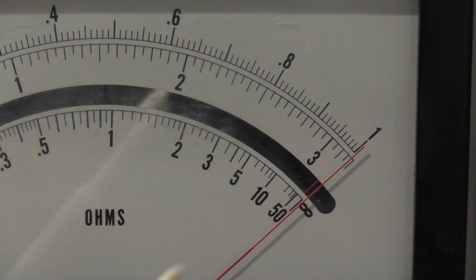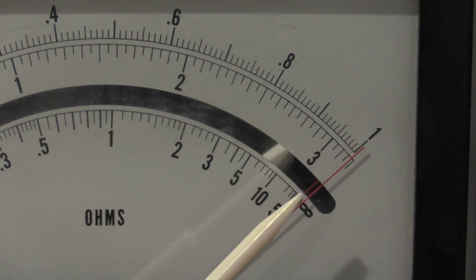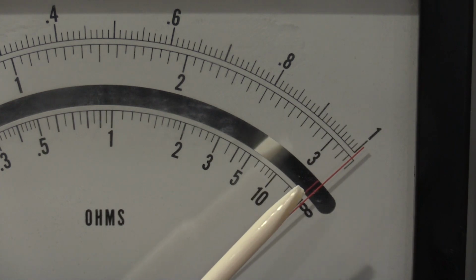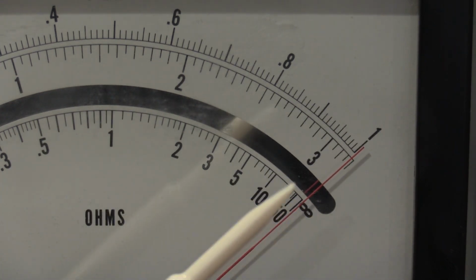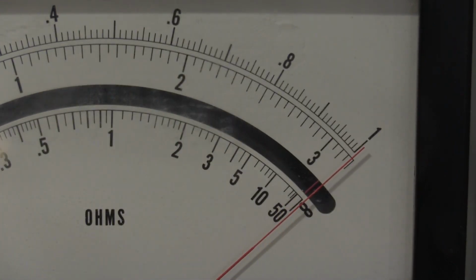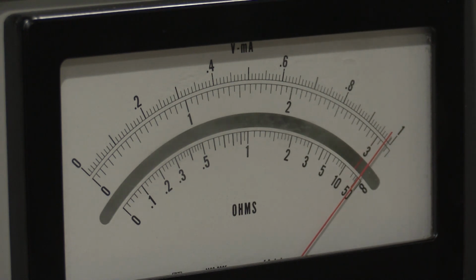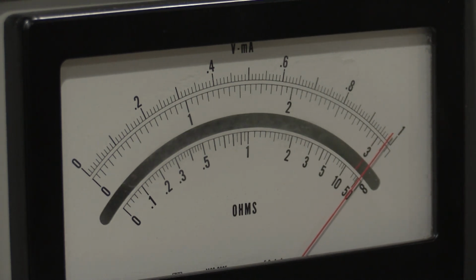You can tell there's a little bit of parallax error in the camera because you see the shadow of the needle in the mirror. When you look at one of these, that's what the mirror's for: you line up the shadow to get rid of the parallax error on the dial face. Okay, our ohms range is off a bit, which is fine. I need to put this on infinity, and I need to make sure none of these leads are connected to anything and we have no leakage paths, because this is a very sensitive meter.